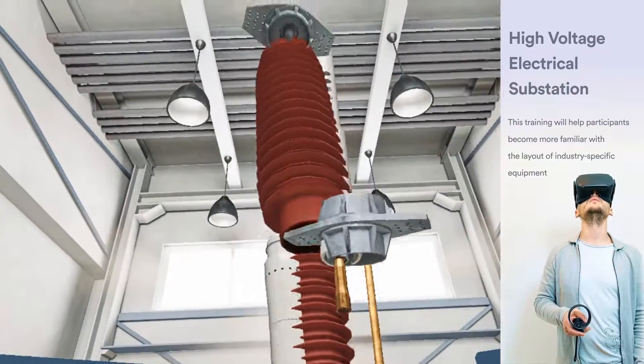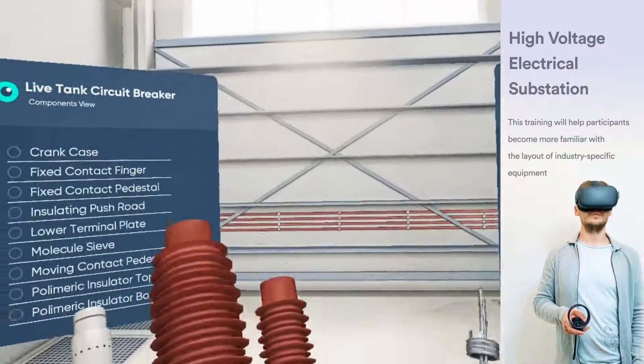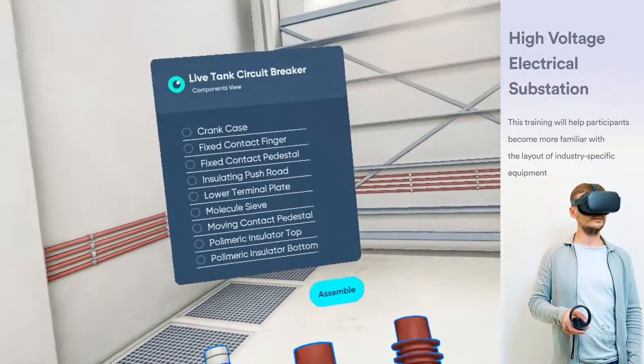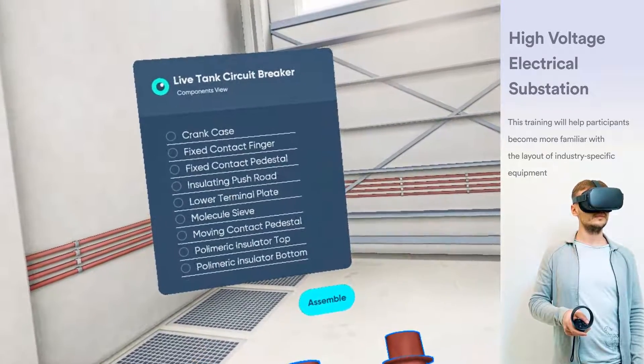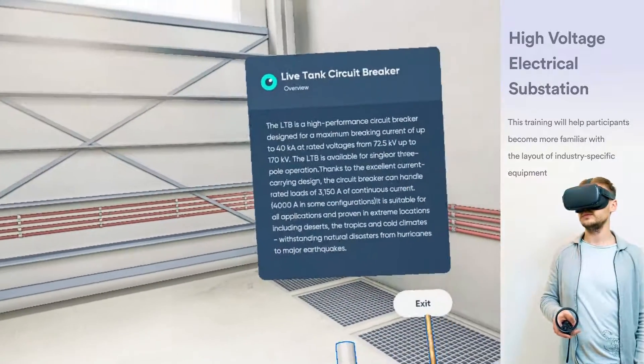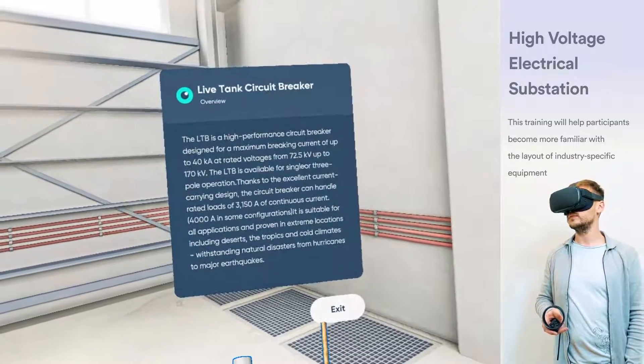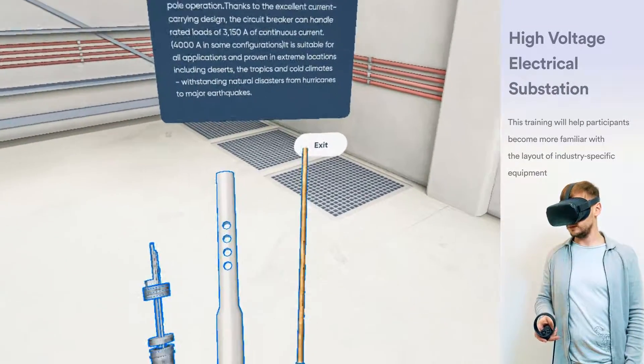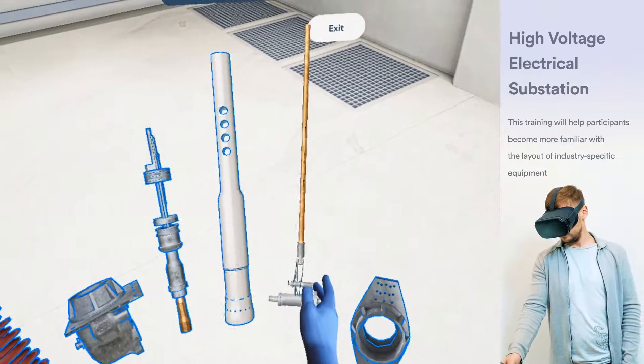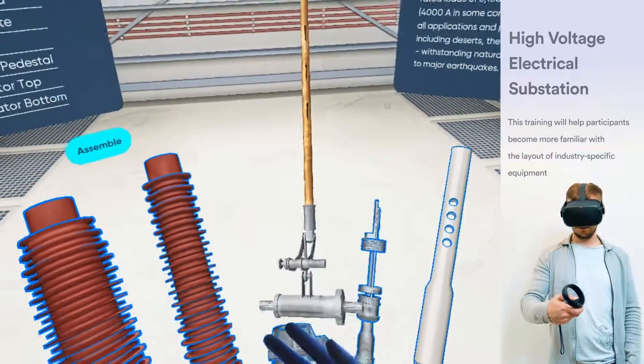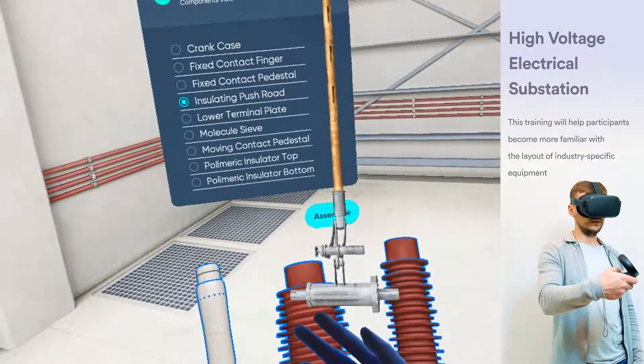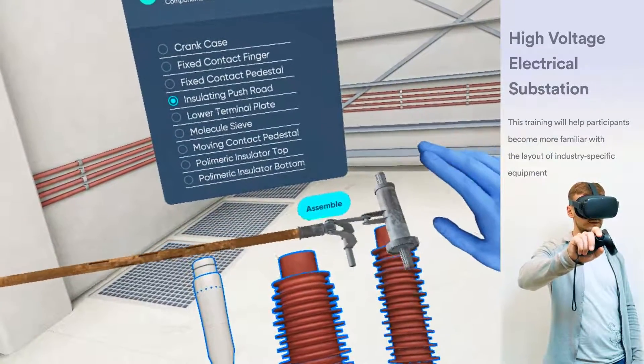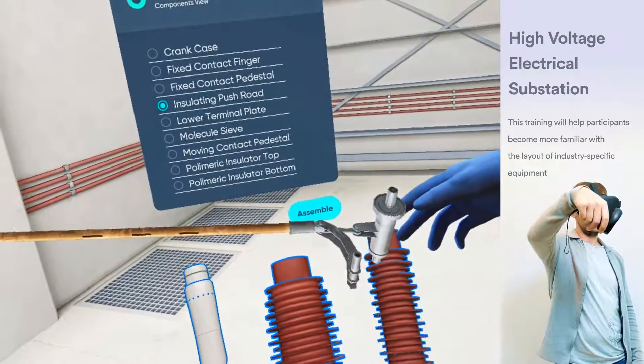The live tank circuit breaker is a high-performance circuit breaker designed for a maximum breaking current of up to 40 kiloamperes at rated voltages from 72.5 kilovolts up to 170 kilovolts. The LTB is available for single or three-pole operation. Thanks to the excellent current-carrying design, the circuit breaker can handle rated loads of 3,150 amperes of continuous current.